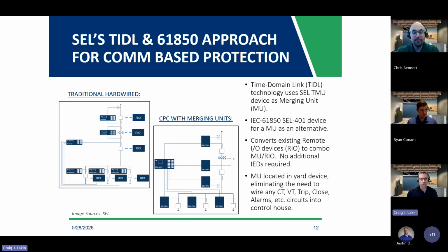And one thing I wanted to show here is that while it looks like, well, when the merging unit design, we're adding in all these merging units. So we might be reducing our number of relays, but we're adding in merging units. So isn't that kind of a wash on devices?